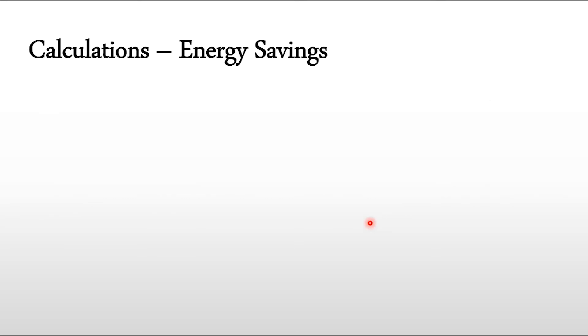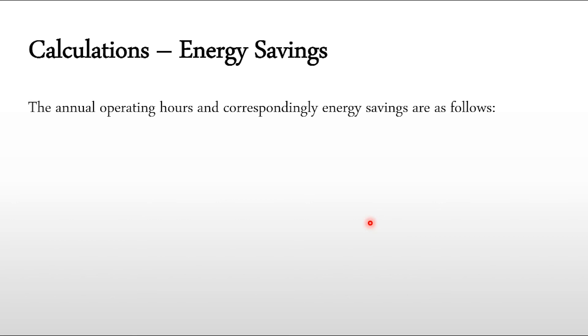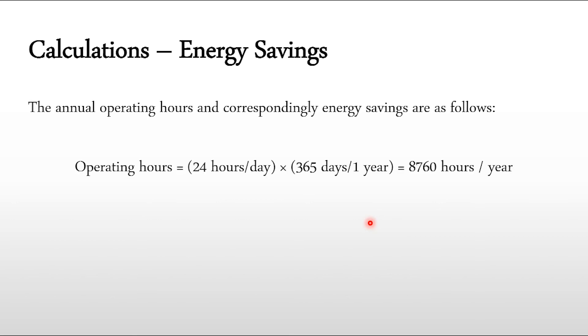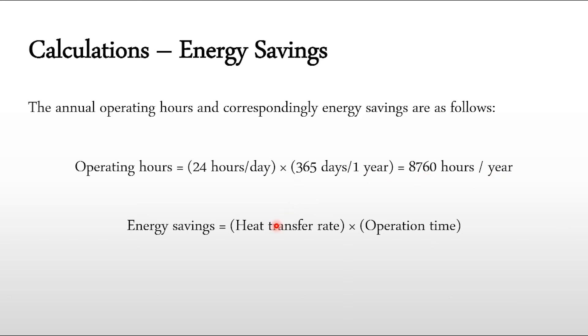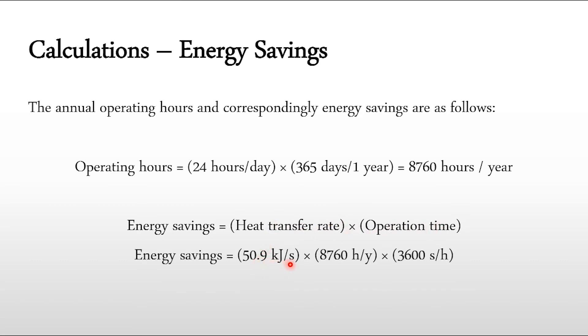Next we calculate the energy savings. First, the annual operational hours: the plant runs 24 hours a day for 365 days, giving 8,760 hours per year. Energy savings = heat transfer rate × operation time = 50.9 kJ/s × 8,760 hr/yr.